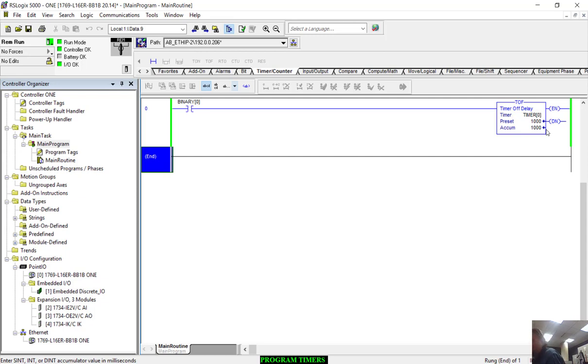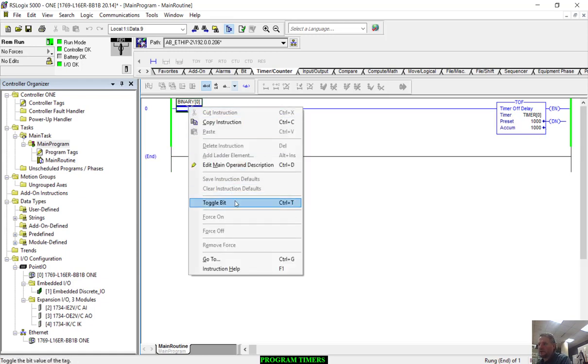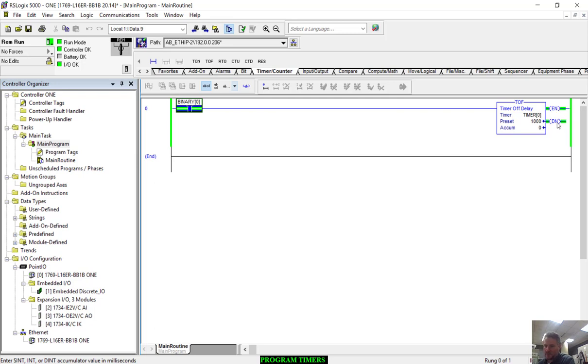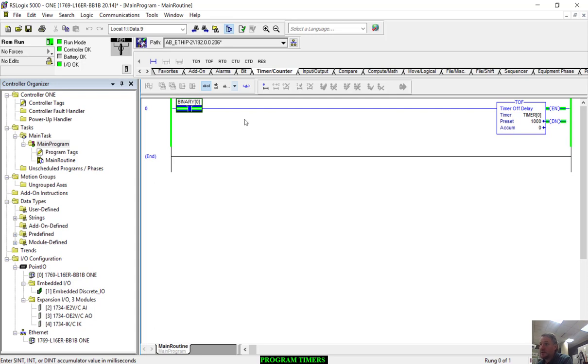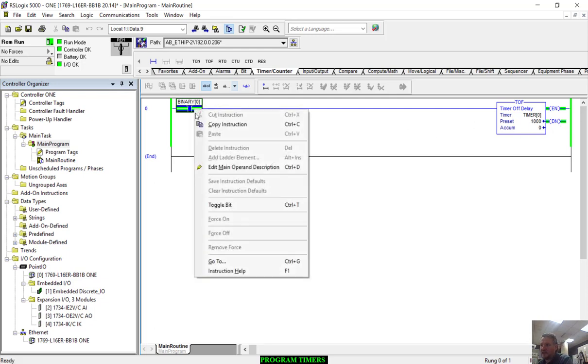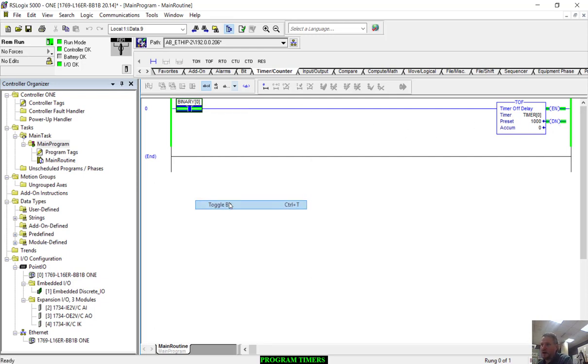Let's watch this closely. I'm going to toggle this bit real quick. The first thing you'll see is the enable and the done bit turn on immediately. Enable and done are on right now. So as soon as the input comes on, the done bit turns on. This is something you need to be aware of. You will be tested on it, I guarantee it. When we're using timer offs, the input turns on and the done bit turns on.